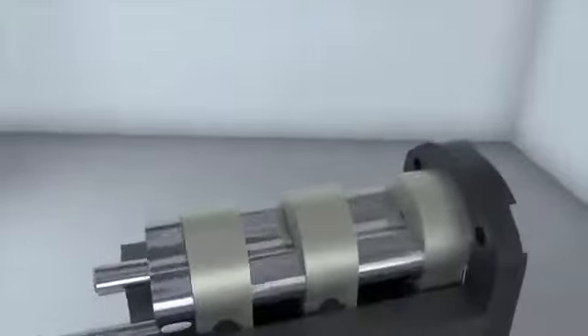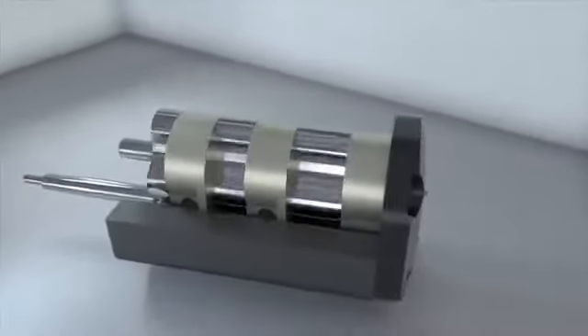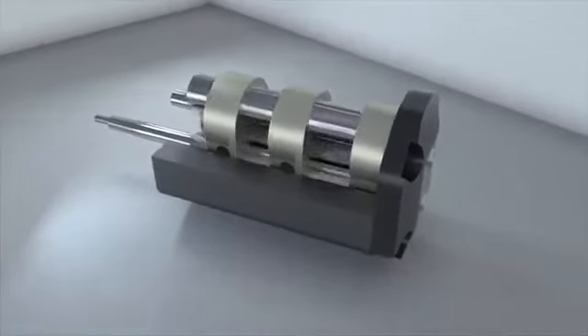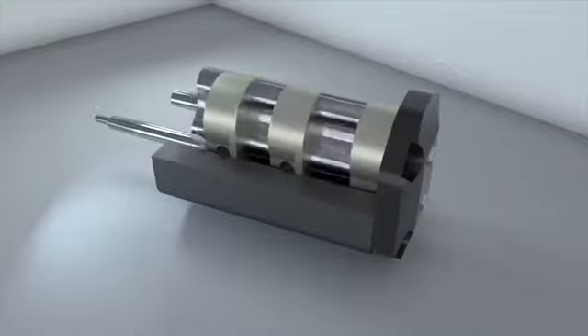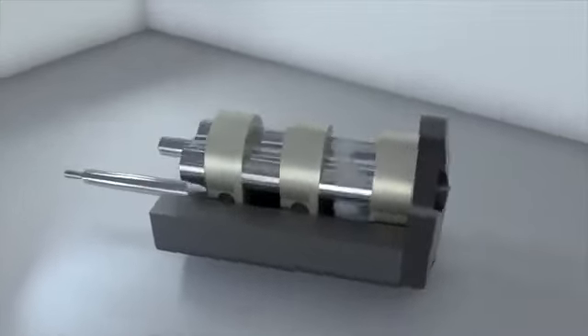Multi-stage roots vacuum pumps can be used to provide the desired degree of vacuum. In this case, several pumping units are installed on the shaft. First, the air is supplied to wide rotors, where its volume is maximal, and then to smaller ones.